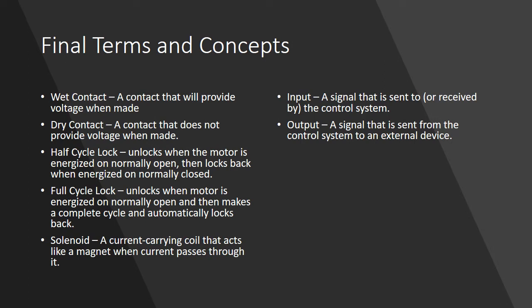There are other terms such as wet contact and dry contact. A wet contact is a relay contact which provides voltage at all times or whenever the contact is made. A dry contact is a contact that does not provide voltage until the relay is activated.